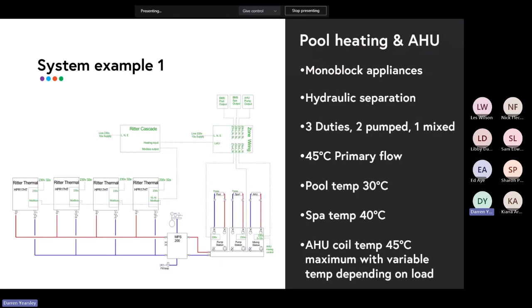There was a gas burner which was in the existing air handler unit, which they removed and replaced with a water coil, and then we connected that onto the system using a mixing station. And the reason why we used a mixing station was the air handler wanted to be able to vary the water temperature depending on the load. So if it's a very low load, they might send 20-degree, 25-degree water to the coil of the air handler, and if it's heavy load, they'll send 45-degree.